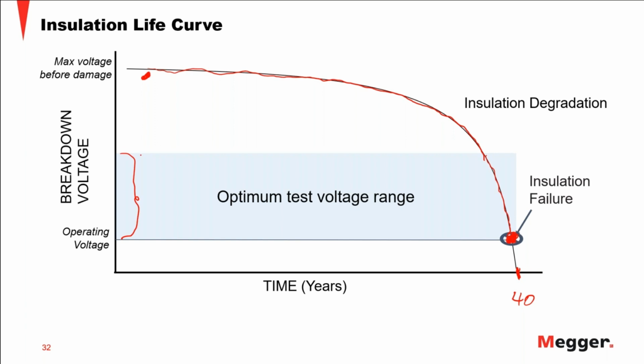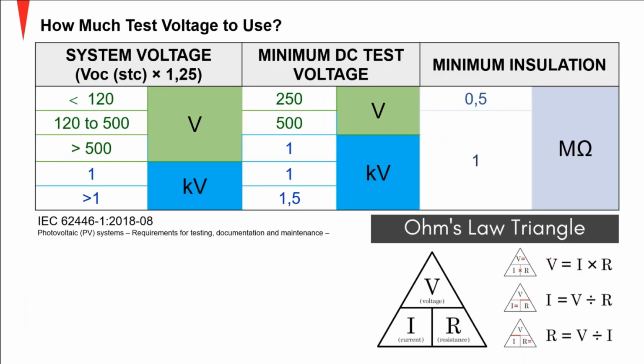It does a quality test. It's not a withstand test. That will be a hypot. With the insulation resistance, we want to get a resistance value. We don't want to see if the insulation is going to break down. So how much voltage to use for the test?